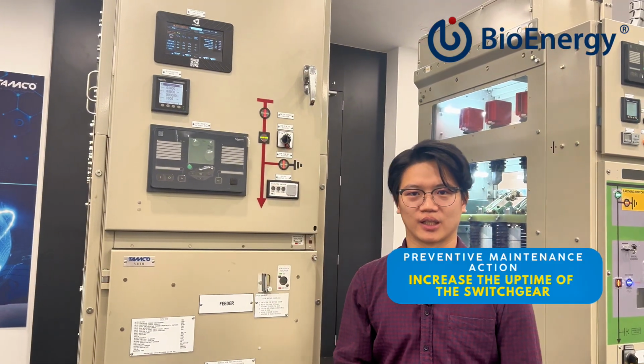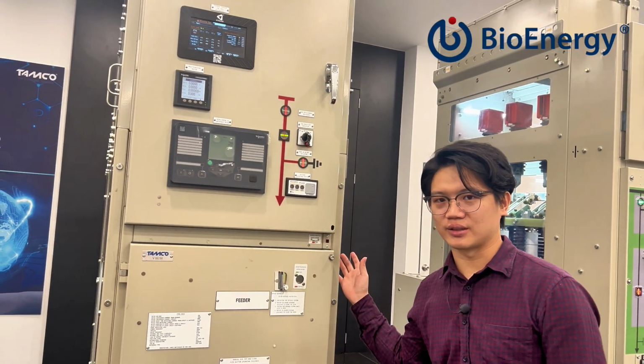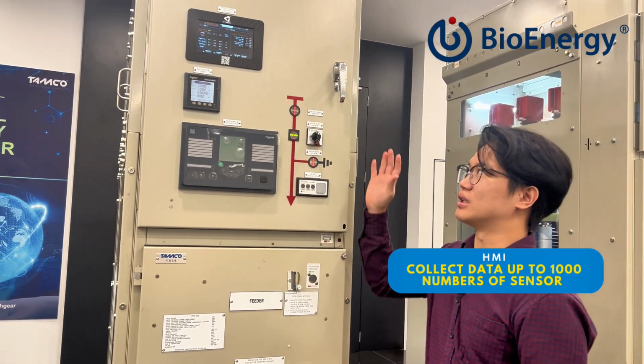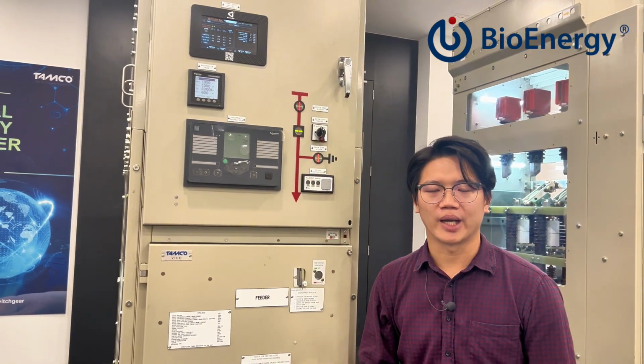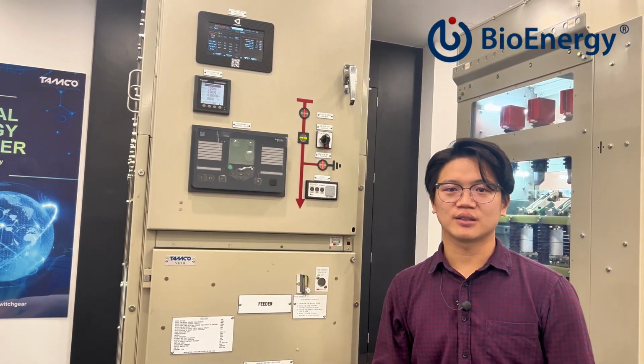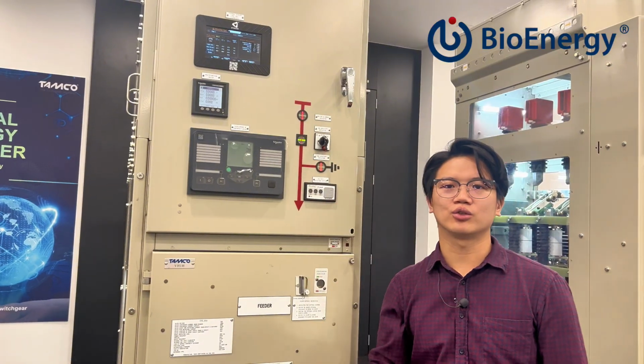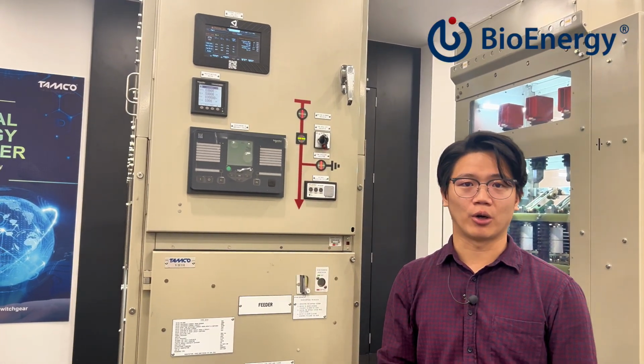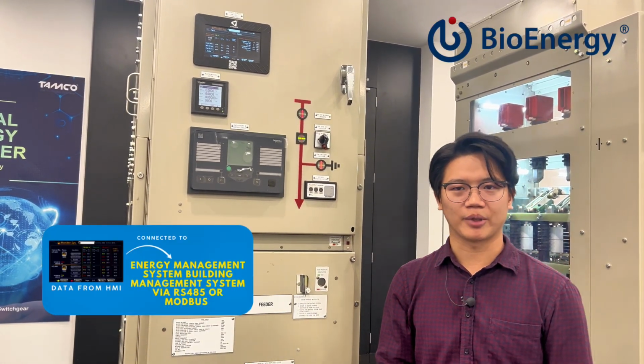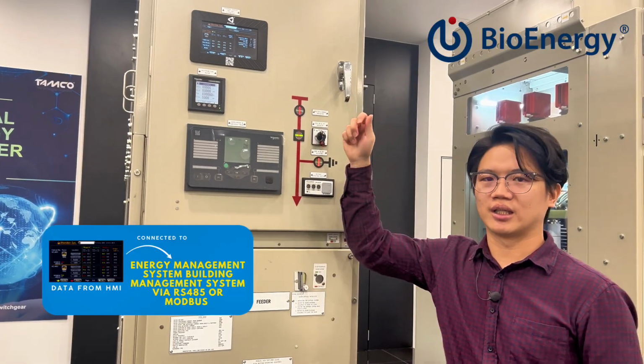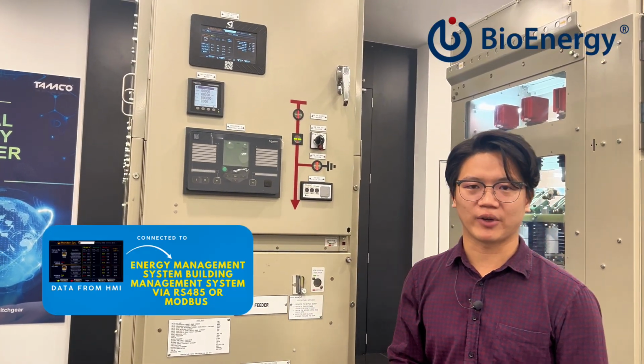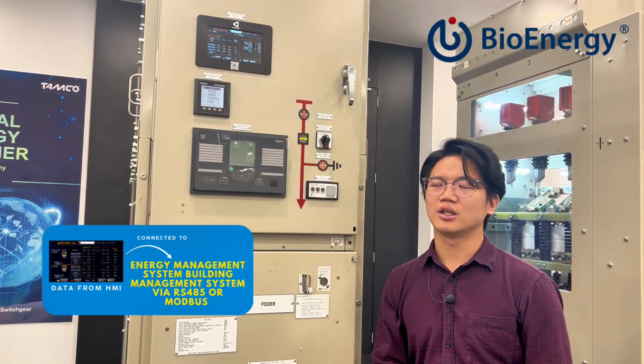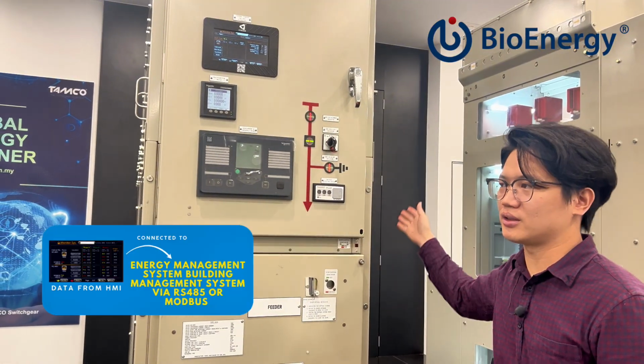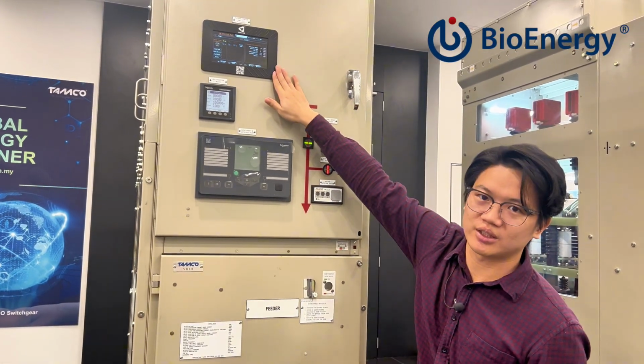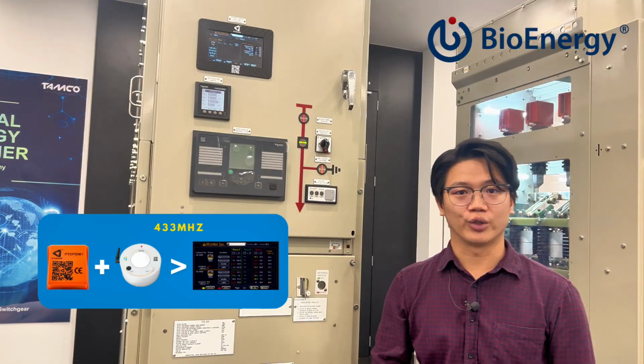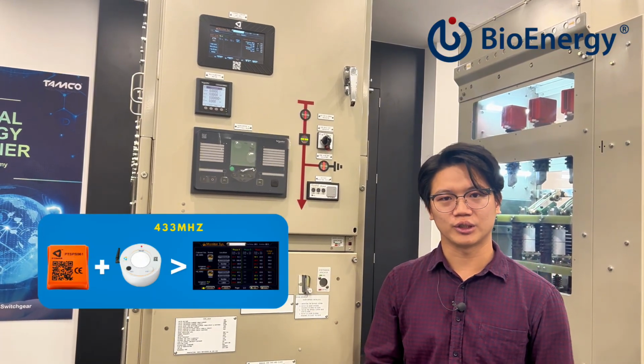This HMI can collect up to 1000 sensors. The data collected in the HMI can be utilized by our clients. If the clients want the data to be sent to the energy management system or building management system, the EMS or the BMS, you can just connect it using RS485 or Modbus connection. So how do all the sensors communicate with this HMI? It's actually using radio wave at 433 MHz.